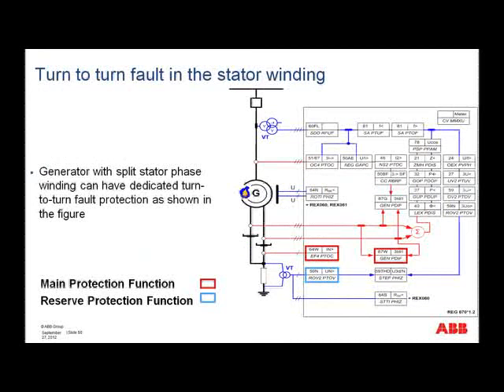Another possibility, of course, for detecting turn-to-turn faults is if you have the split stator winding. One option is then to look at the unbalance that you would get here in the star point from the two windings. And another possibility is to make a differential function between the current flowing in the two windings. To do that, you would have to bring these CTs in separately.